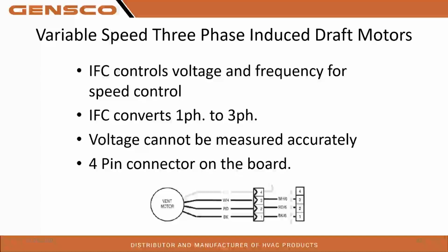Okay. I will tell you on the variable speed units, if you have a leak in the heat exchanger, that motor will do whatever it has to do to try to pull that switch in. So if you call and you say, I have this variable speed inducer motor and it is just going gonzo fast and it can't make that pressure switch, you've got a leak somewhere. You've got a leak in the heat exchanger somewhere. You've got a leak in the RCT fitting behind the inducer, something, right? Because it is going to try to ramp up and make that switch, versus a standard motor, which doesn't care, right? The speed it runs at, the speed you get. So there is a 4-pin connector on the board for this guy.